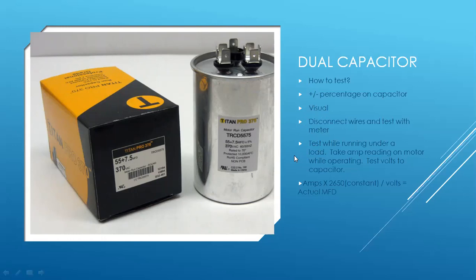Now the best way to check it is to test it while it's under a load. If you check it with the power off and leads disconnected, you're just checking a sitting capacitor. But you can also check it while it's running, and that checks it under a load, so it gives you a little more accurate reading. The proper way to do that, basically you have your amps. So whatever you're checking, if you're checking the compressor, you're going to check the Herm wire. You take those amps. So we'll just say whatever it is, 10 times, this is a constant number here, and this will fluctuate slightly, but 2650.